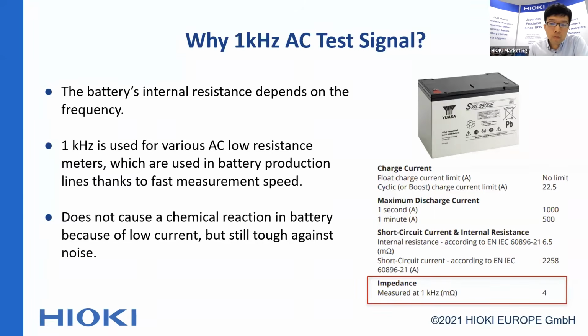However, the purpose of maintenance is to find the deteriorated battery in the UPS system quickly. The 1 kHz signal method is faster than the DC measurement method, and there is no discharge of the battery during the test thanks to the small test signal. Test speed is important for the battery manufacturer and also for the maintenance situation. As a result, the 1 kHz inspection has become the industrial standard.